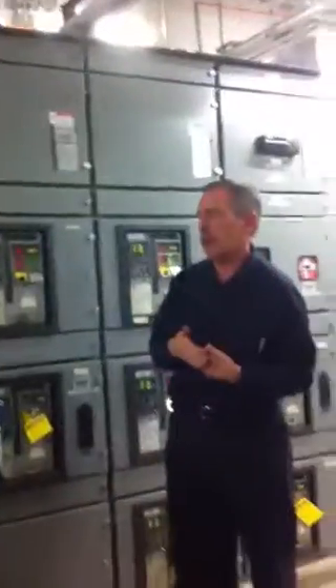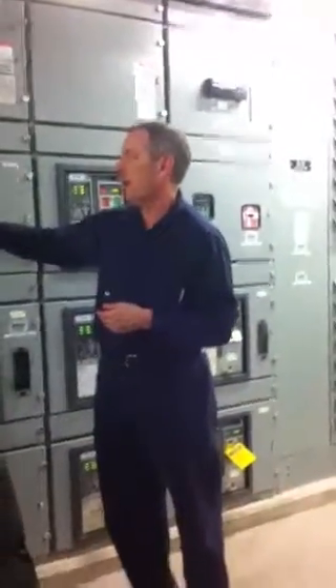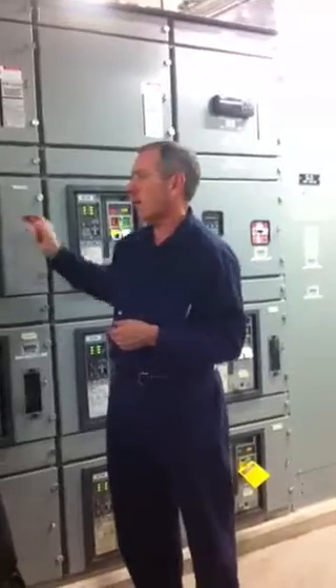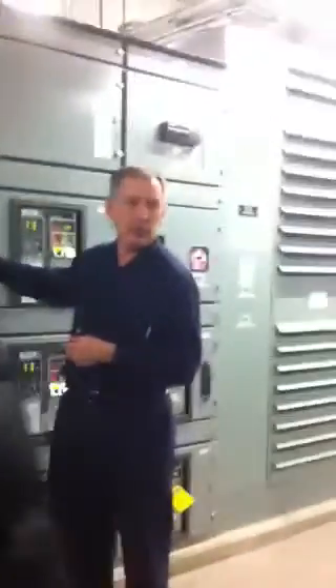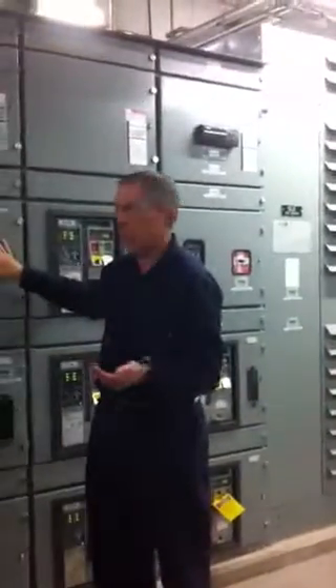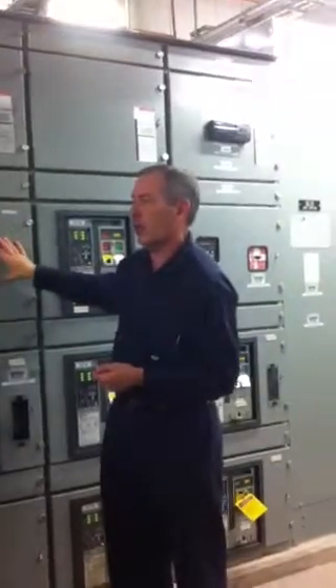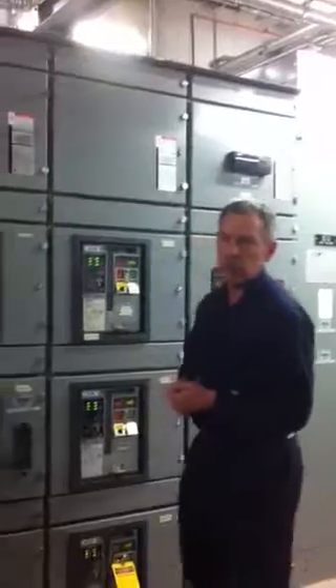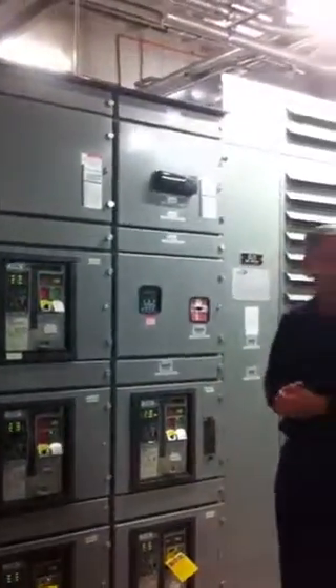of these protection relays, the coordination study is handed over to a group that will come in here and dial in the settings. They will put their secondary injectors on the CTs, they will inject the current and see that the breaker trips at the setting that the coordination study shows, and then once we get that commissioning report, our group will start to energize the facility. So there's quite a process to it from day of inception to the day you turn it on.